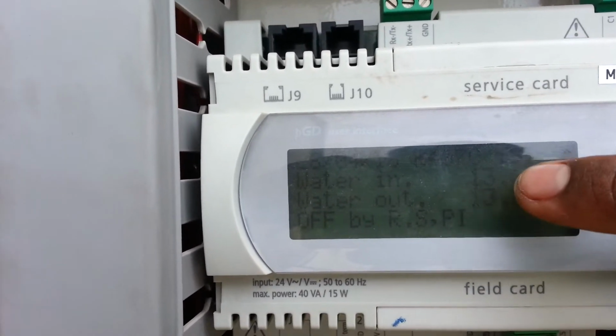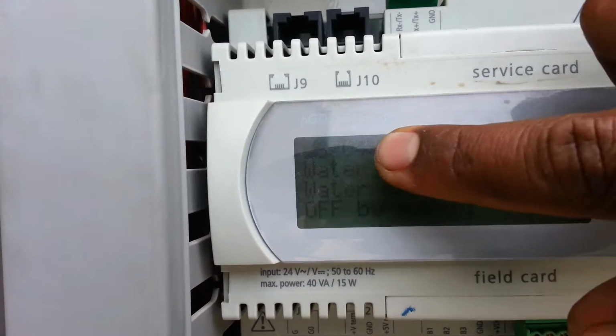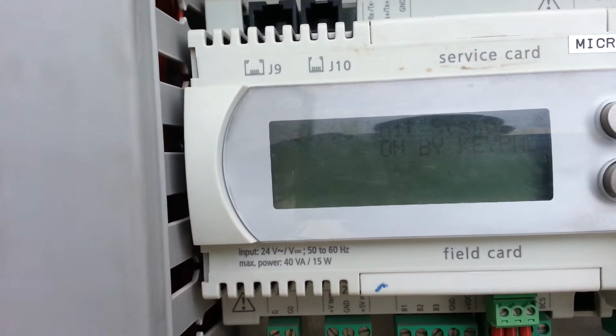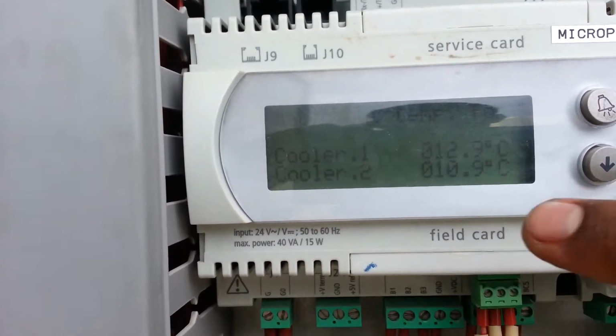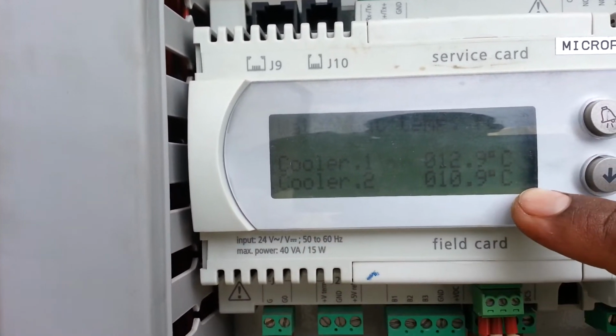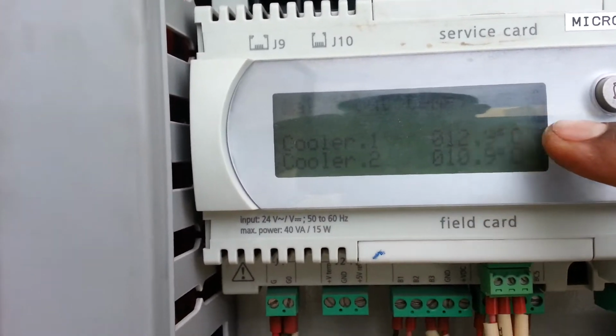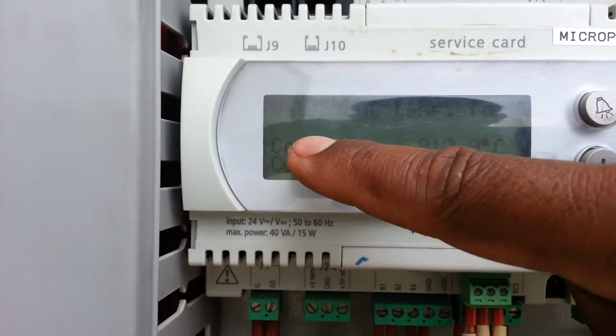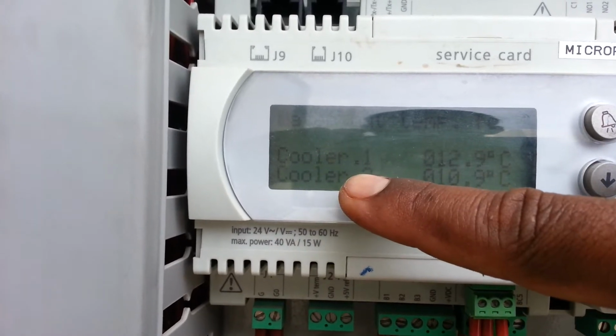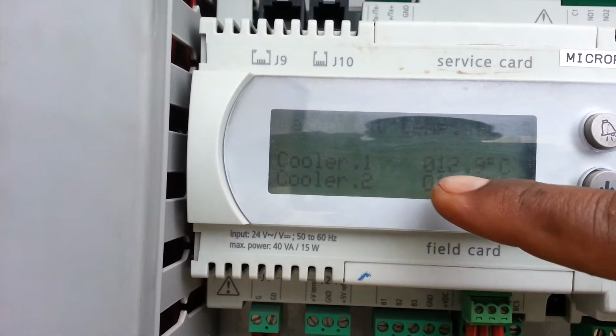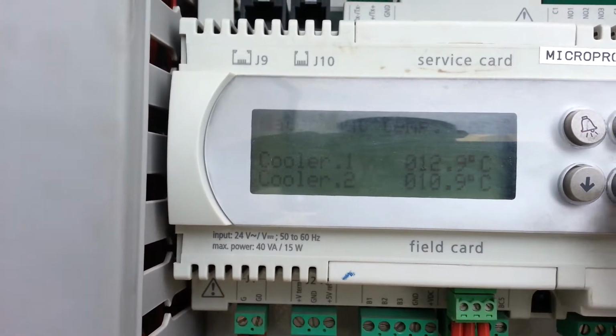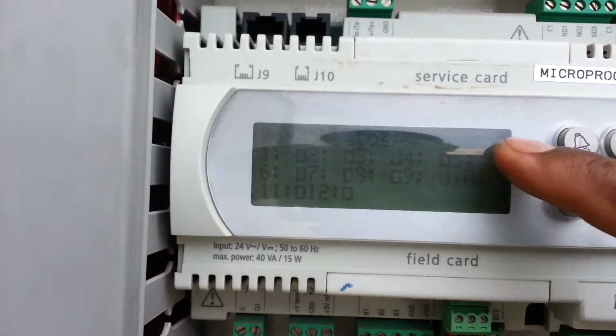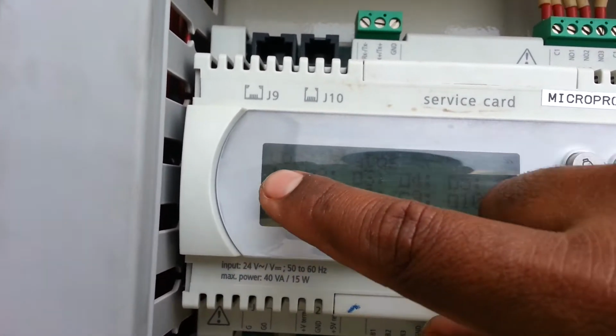Here you can see the water in and out. This is the chilled water line in and out. And this is the ambient temperature. And here are the cooler 1 and cooler 2 temperatures. This is the water out temperature, cooler 1, cooler 2. This chiller has 2 coolers. And here is the compressor status. It contains 2 Copeland scroll compressors.